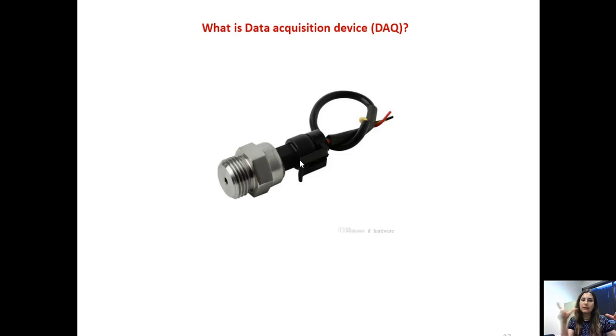So you just have to find a linear conversion from volt or current to whatever the actual reading is on this sensor. So for example, if you have a thermometer, a thermocouple, or something that measures a temperature, and it can measure a temperature from 0 to 100 degrees C, and that reading in terms of volt is from 0 to 3 volt DC or from 0 to 5 volt DC. What it means is that 0 degrees C is 0 volts and 100 degrees C, for example, is 5 volt DC.